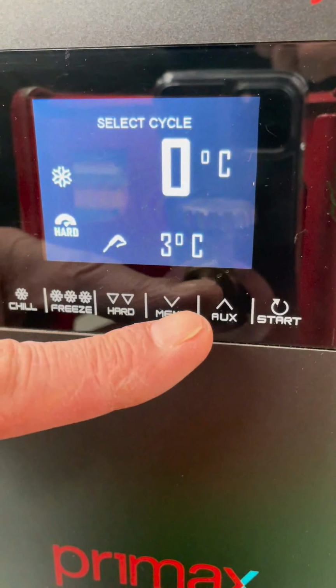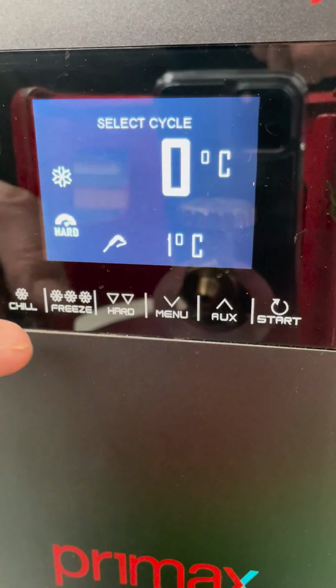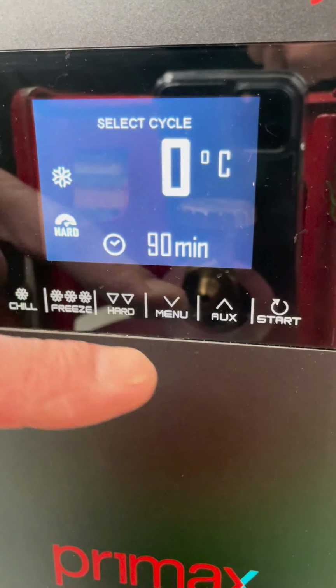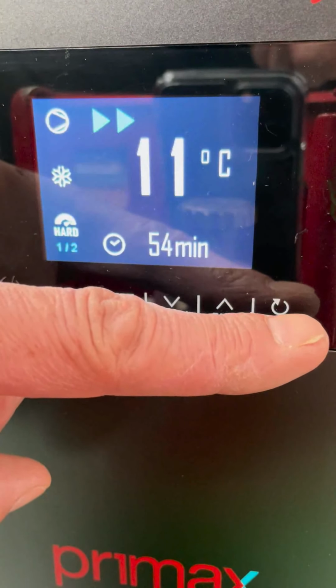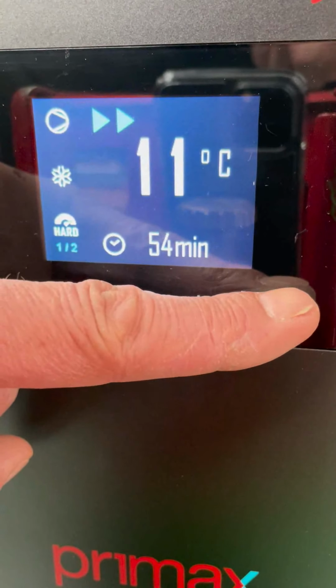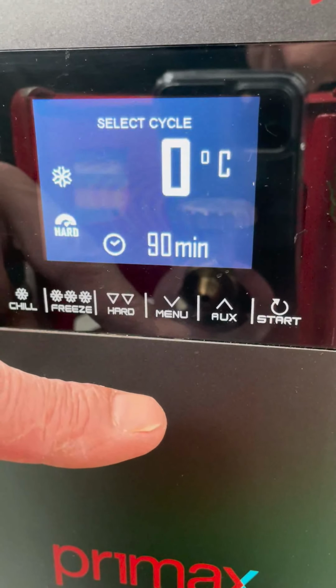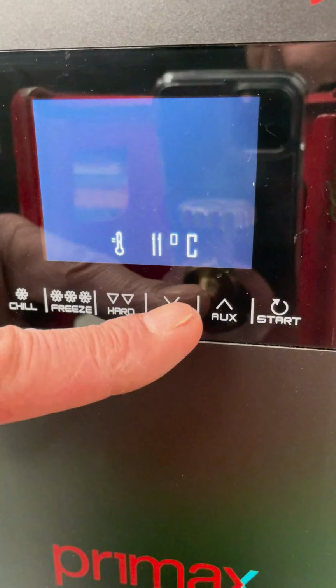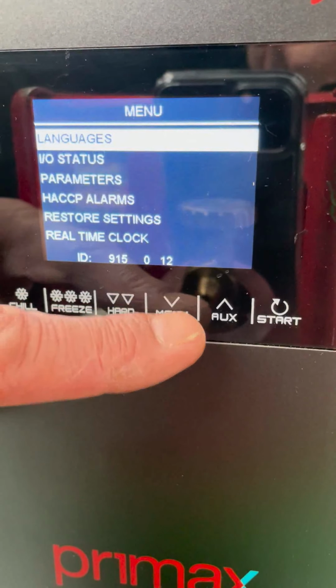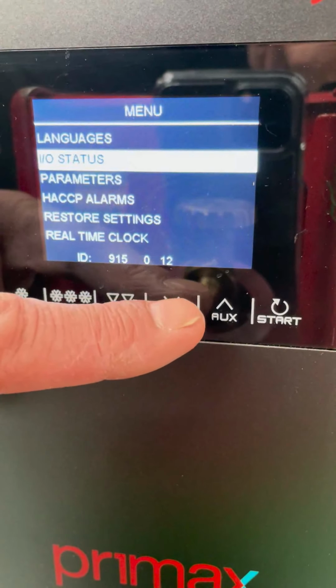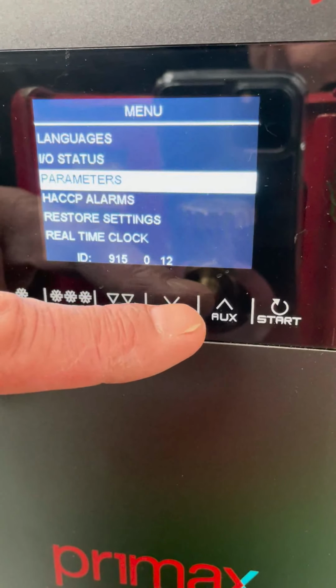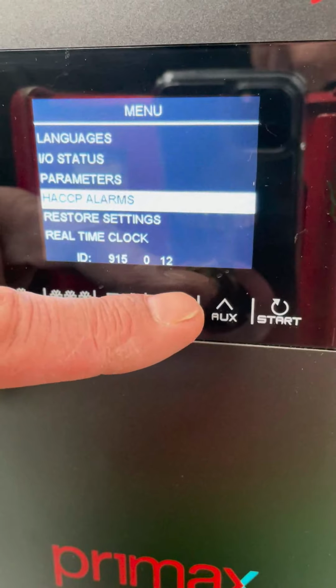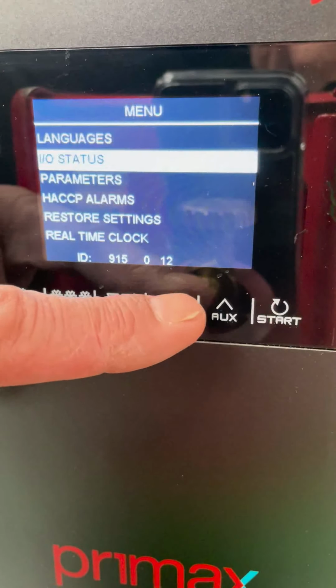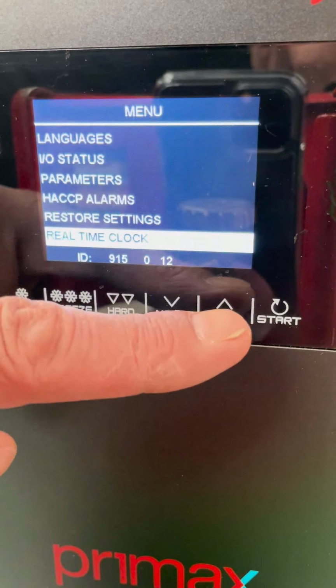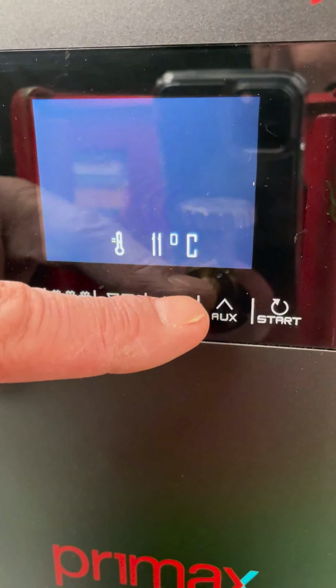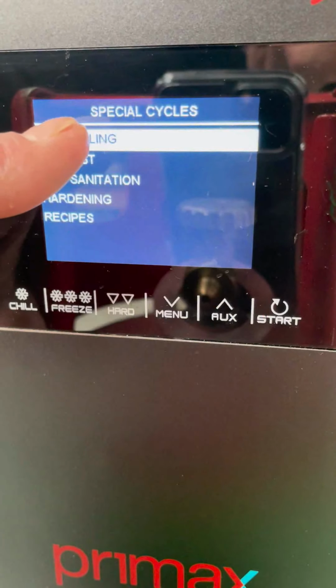Okay, then there is another nice button, menu. Sorry, I need to go back because now it's telling me to change the time. I stop the cycle, I wait for the standby. Yes, menu. You can change the languages, you can check the relay status on, off, you can modify the parameters, you can see the HACCP alarms, you can go back to the factory settings, or simply adjust the clock. This was the menu. Aux, before you have seen pre-cooling and defrosting.